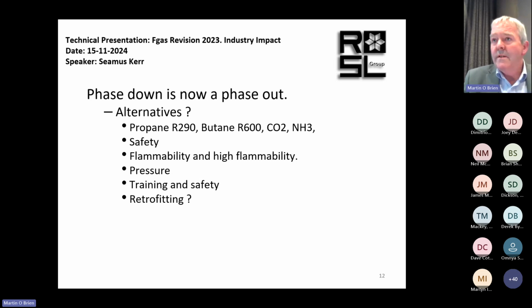Then CO2 is an option — very high pressure, high energy user. In Southern Europe, as temperatures rise, CO2 is becoming less and less efficient, unfortunately, and in the south the carbon footprint of CO2 plants is going to be quite high. But in fairness to manufacturers, the quality of equipment is much better — variable speed drives, good condensers, and so on. We're actually seeing a CO2 plant today is much more efficient than one from 5 years ago, and definitely much more than one from 10 years ago.